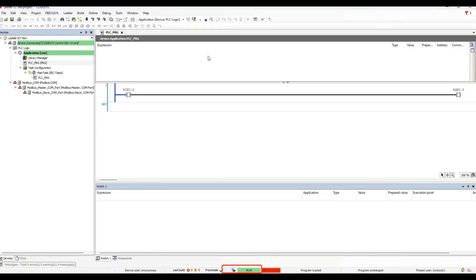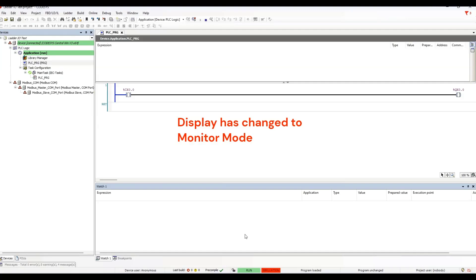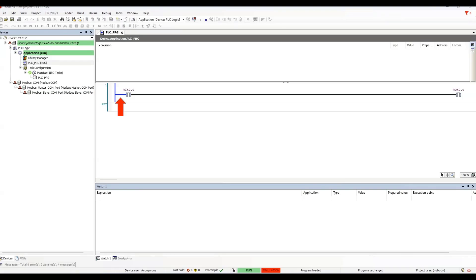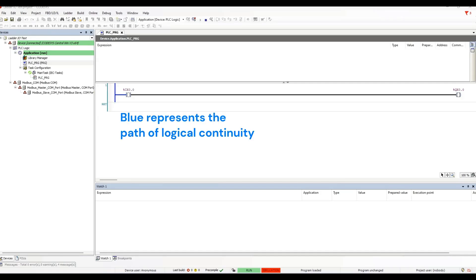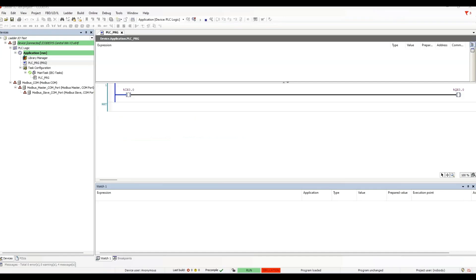So, now that we are online, the display changes from edit mode to monitor mode. When logging in, you may have noticed a change to the display here in the workspace. The vertical line, sometimes called the rail, is highlighted blue. The horizontal line to the left of the contact is highlighted blue as well. The blue line represents the path of logical continuity. It is the path of true conditions that could enable an output if all conditions are satisfied.